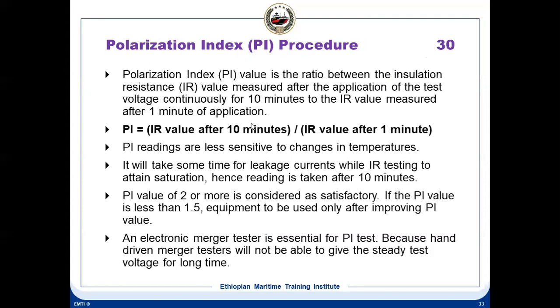So the PI is a ratio between the insulation resistance value measured after application of test voltage continuously for 10 minutes to the value measured at 1 minute. How are the values taken? First you apply the voltage for 1 minute, keeping the time, and record the insulation value you got. Let's say you got 90 megohms in 1 minute. Then you apply for 10 minutes and take one more value.